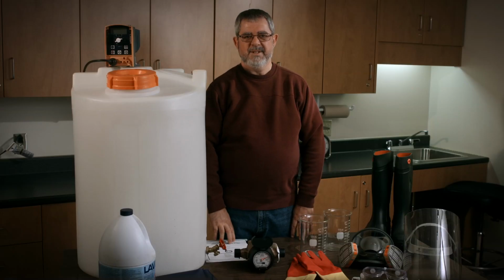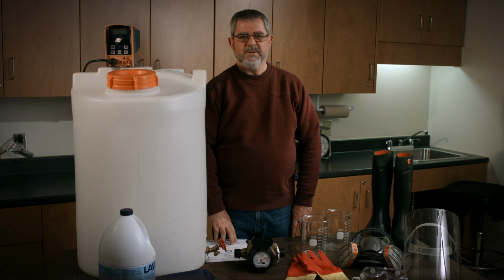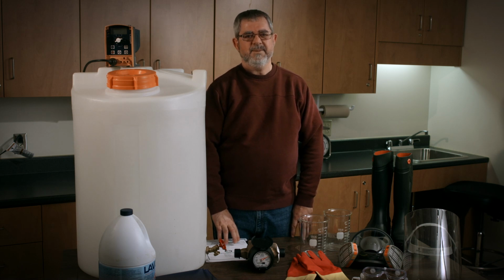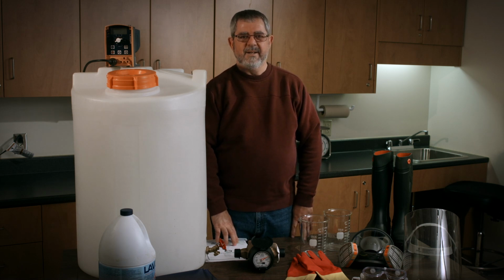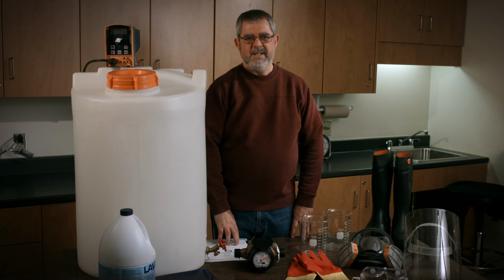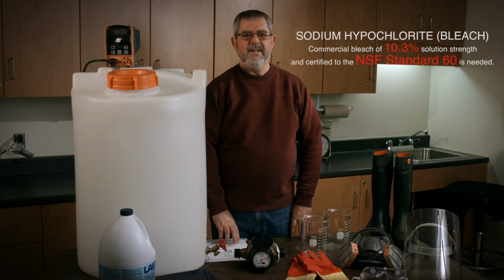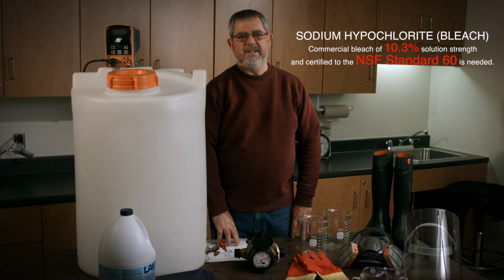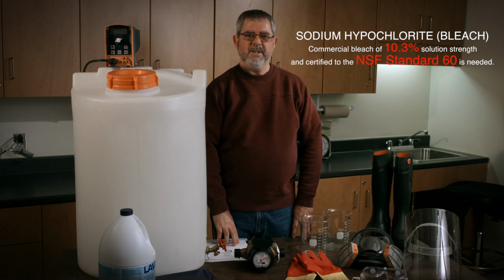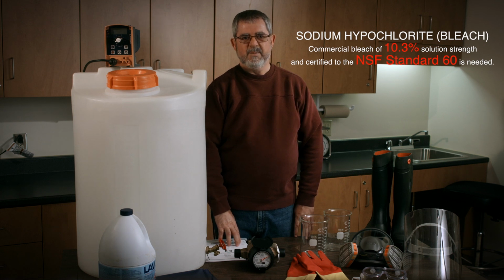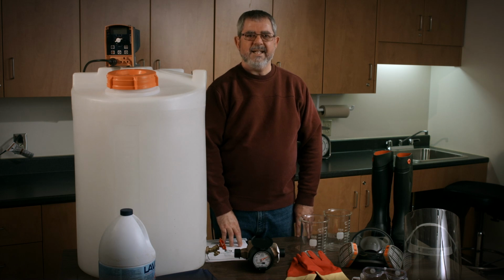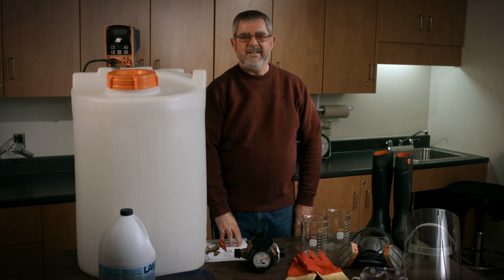The chemical being used today is sodium hypochlorite. It is a common household chemical, also known as bleach. Bleach can be bought in grocery stores where the solution strength is approximately 5.25%. For drinking water disinfection systems, a stronger commercial product of 10.3% solution strength is used. The sodium hypochlorite product has to be certified to the NSF Standard 60.